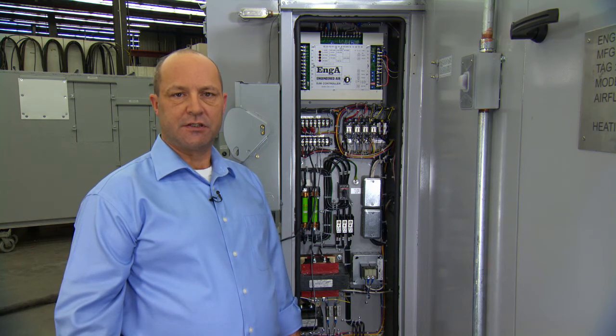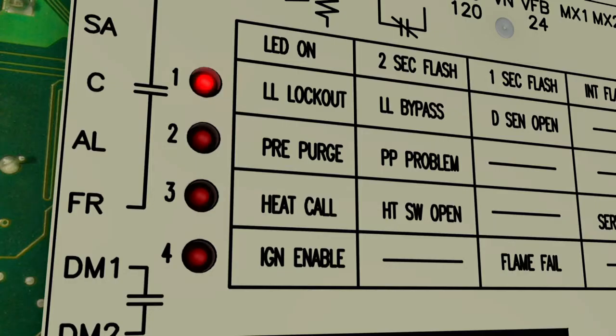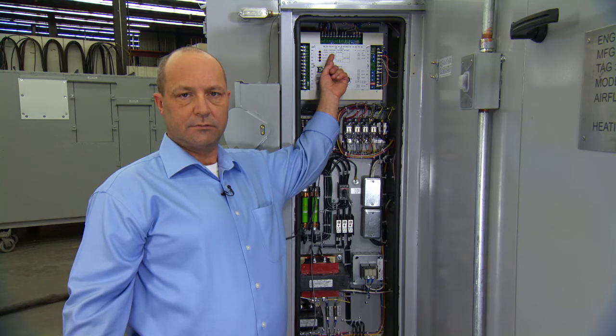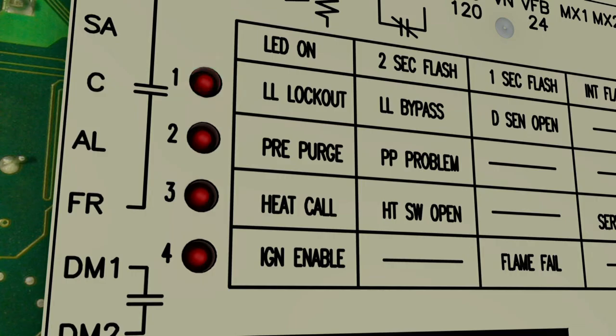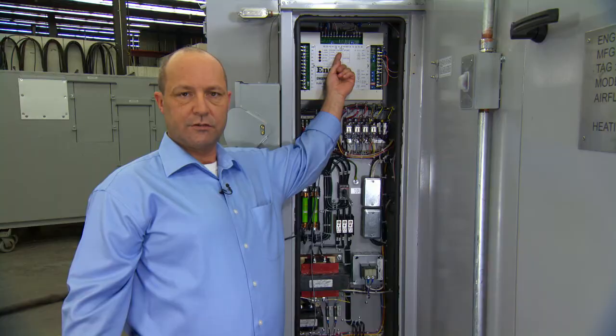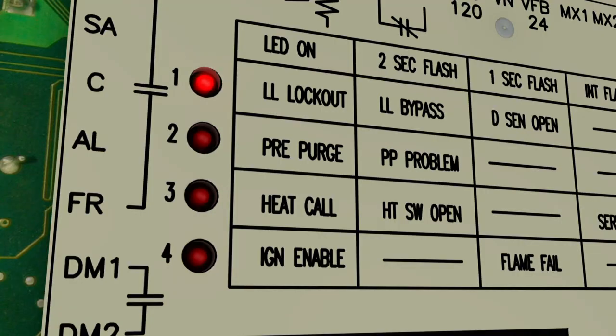What do various flashes of lights mean? Number 1 light, on steady. The unit has had a low-limit failure, meaning the discharge air was below 40 degrees Fahrenheit, or 4.4 degrees Celsius, and is locked off. To reset, turn the service switch in the unit control panel off and then back on. 2-second flash. Unit is in low-limit bypass mode. This will be on for about 7 minutes when unit is first turned on. 1-second flash. Indicates the discharge air sensor circuit is open. Disconnect the discharge air sensor from the board and ohm it out. Compare the reading to the sensor resistance chart in the DJM-3 manual.